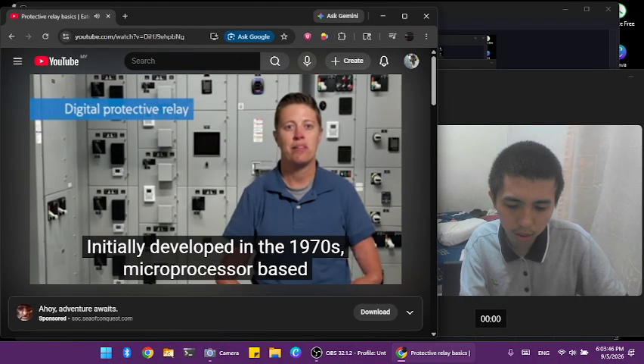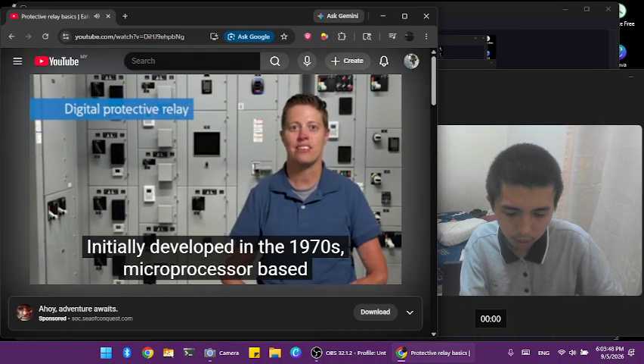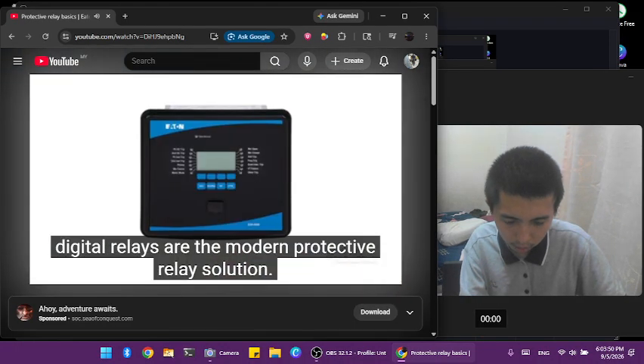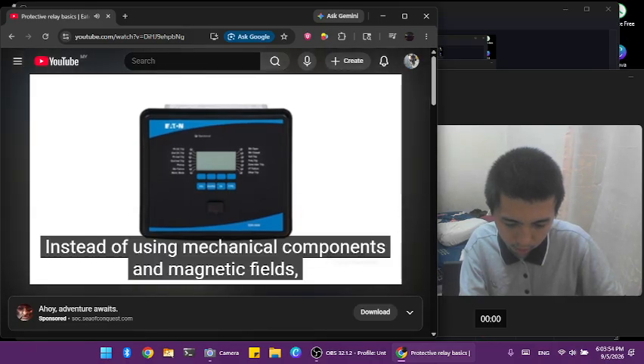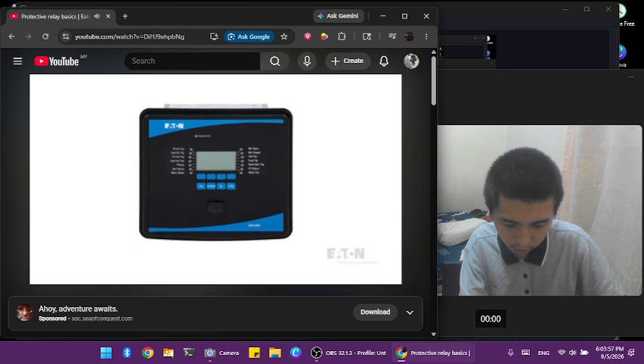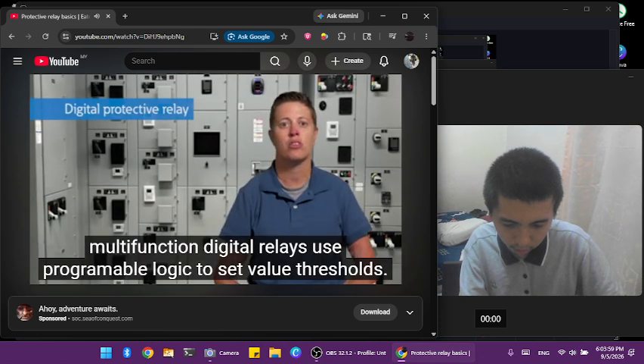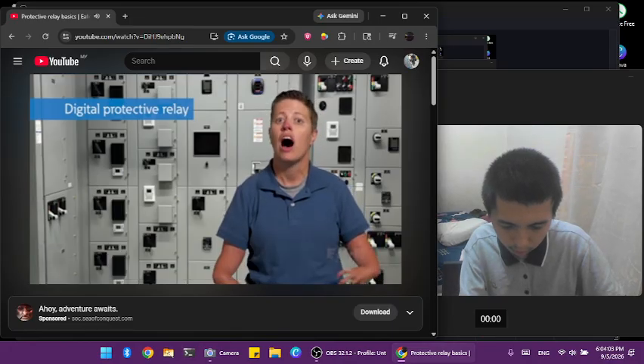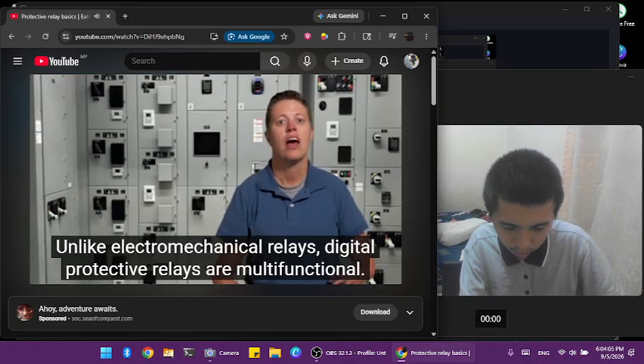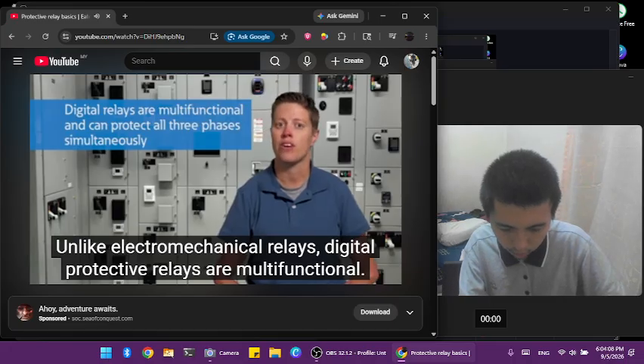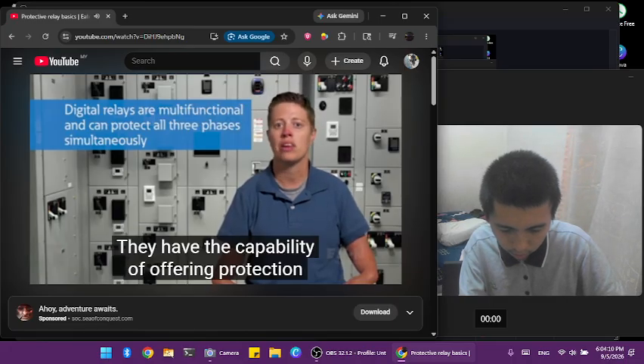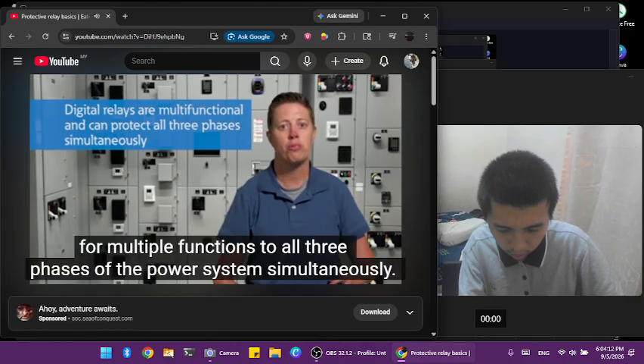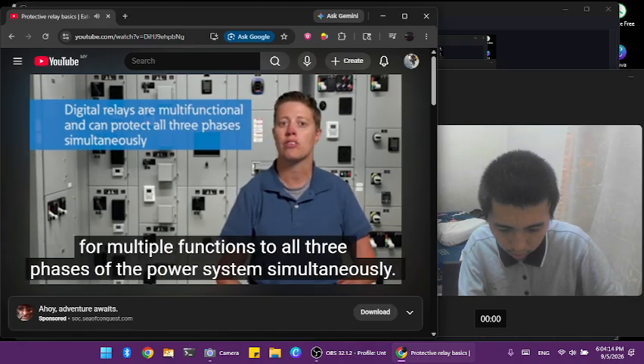Initially developed in the 1970s, microprocessor-based digital relays are the modern protective relay solution. Instead of using mechanical components and magnetic fields, multifunction digital relays use programmable logic to set value thresholds. Unlike electromechanical relays, digital protective relays are multifunctional. They have the capability of offering protection for multiple functions to all three phases of the power system simultaneously.